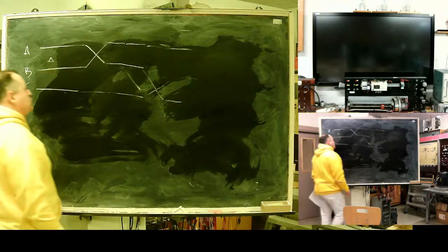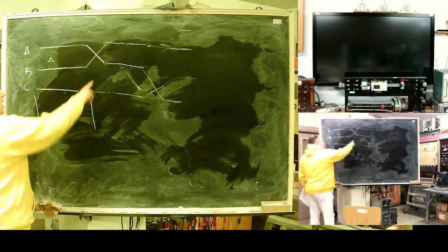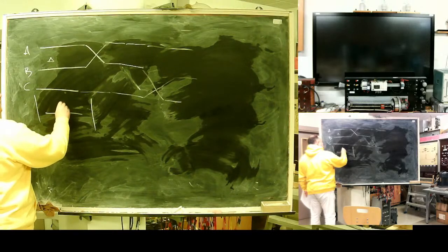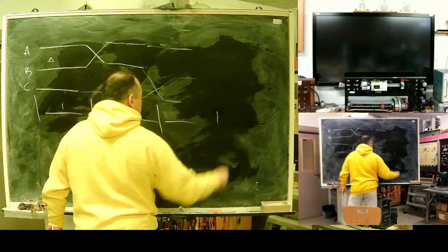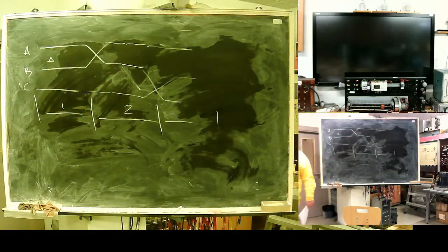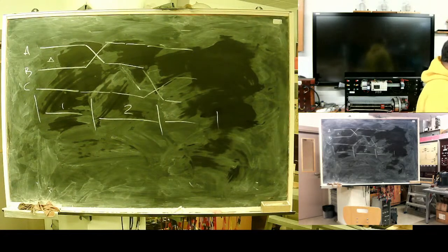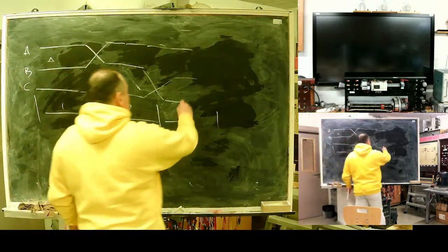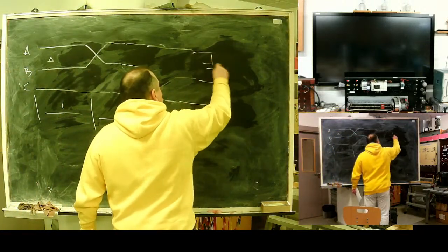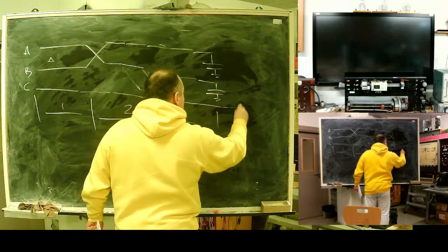Second swap, and so on. I will have one transposition barrel, say one, second transposition barrel, and so on, until the phases do a full cycle. It's done, in reality, to equalize, I will repeat, to equalize capacitance between phase and ground.